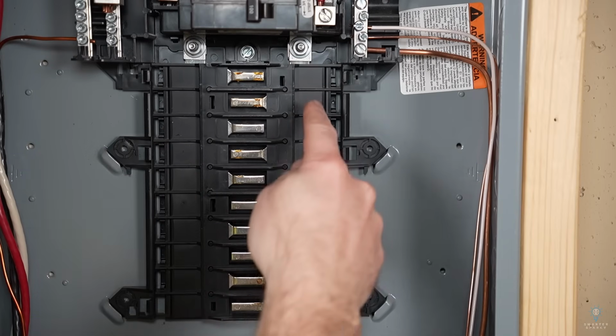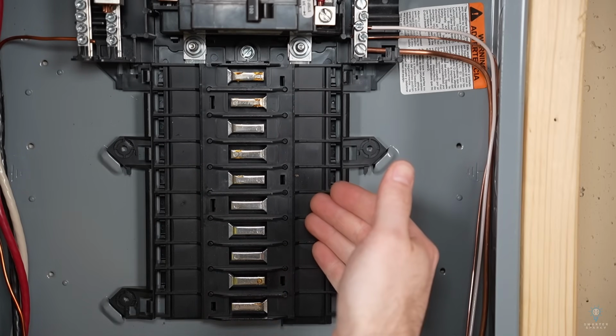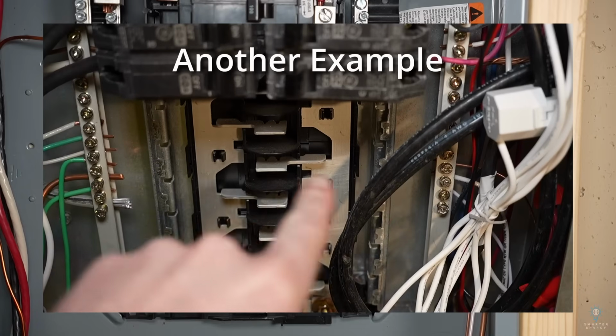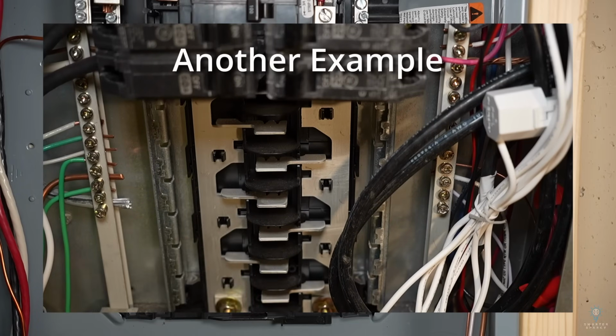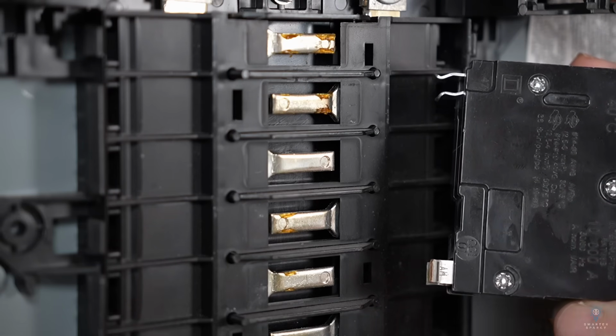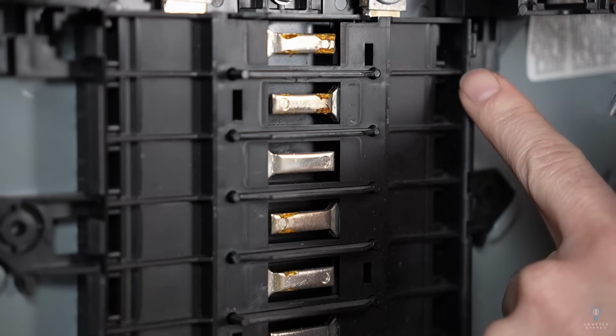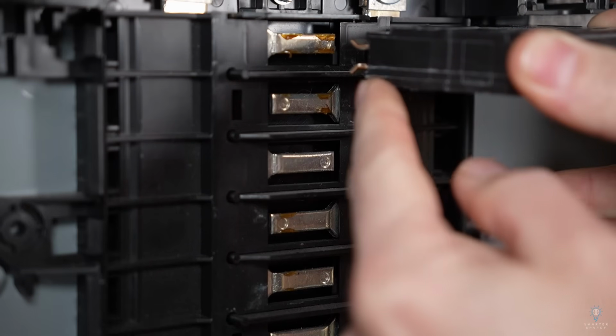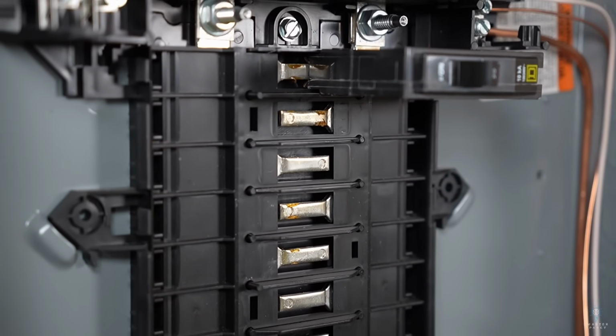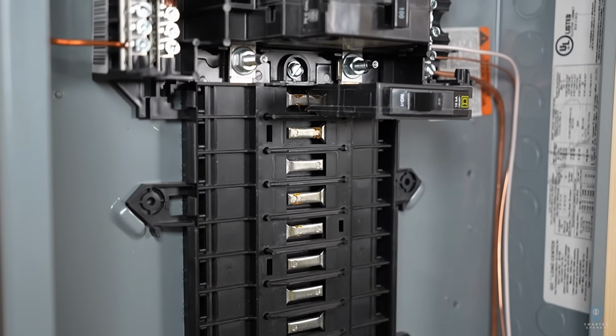This style panel does a great job of physically covering up the bus bars. But this panel has exposed bus bars, making it even more dangerous to work in when live. In this panel, breakers are installed by snapping one side of the breaker into this plastic support bar, and the other side pivots and snaps onto the bus bar. Heavier duty panels might use bolt-in breakers, but the concept is the same.